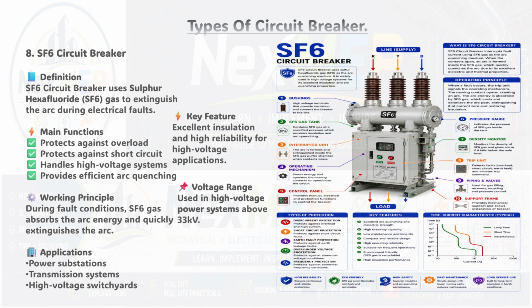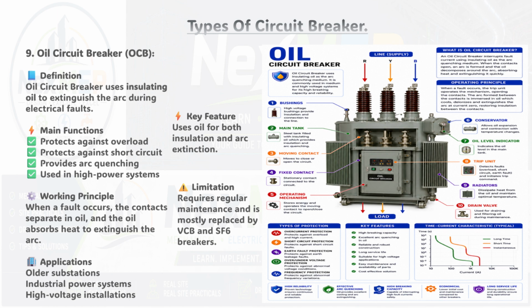Key features: excellent insulation, high breaking capacity, low maintenance, compact design, and SF6 gas is recyclable, so it's also environment friendly. One thing to note: SF6 gas is non-flammable, non-toxic, and pressure is continuously monitored inside the tank by a density monitor. Last but not least, the oil circuit breaker, or OCB.